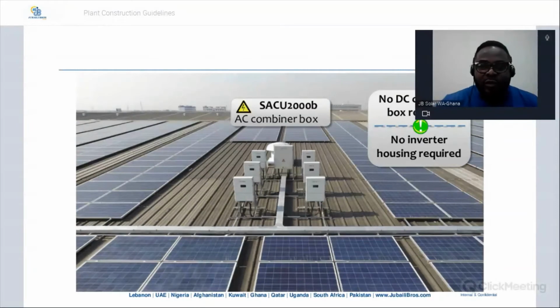Now let us go through a few things that we expect you to do, and things we don't expect you to do. Huawei inverters are IP67 rated, IP66 for some, so you can position these inverters without a housing, and it will not be a problem. However, it is our recommendation that you always put a shade above your inverter. This is mostly common sense engineering - even if the inverter can handle harsh weather conditions, put a shade over it to prolong its lifespan.